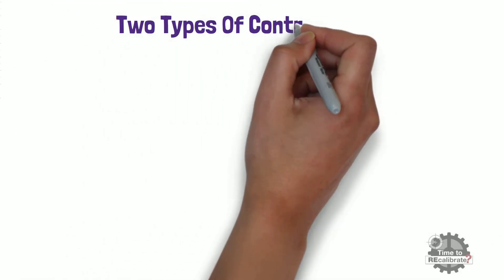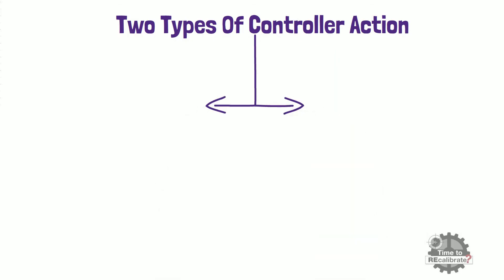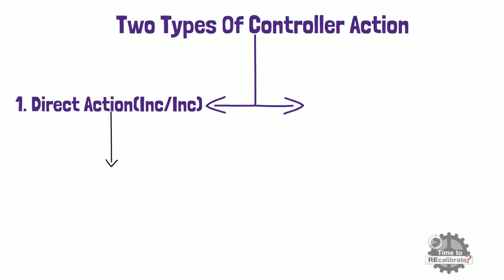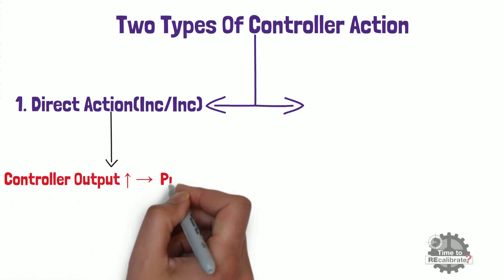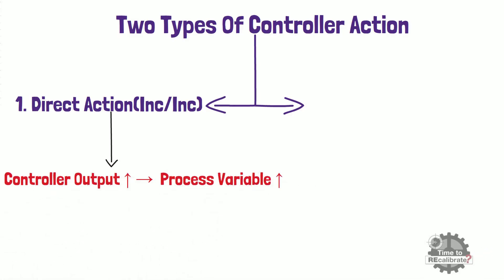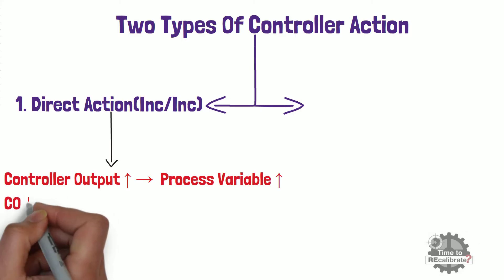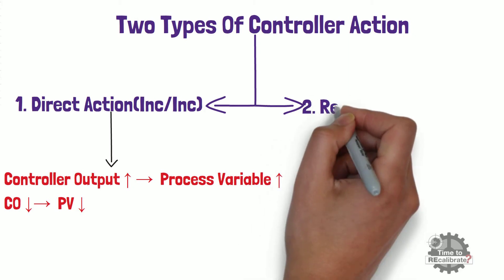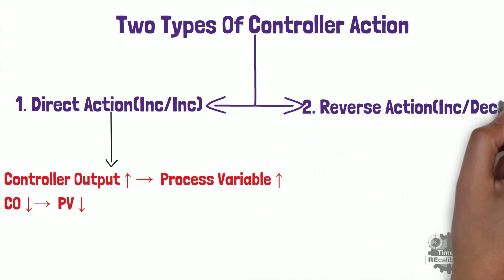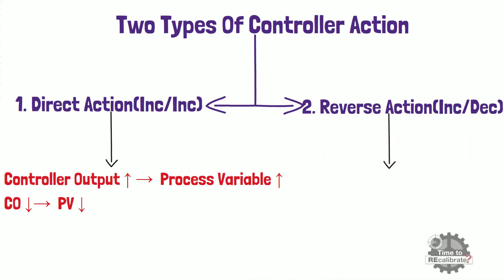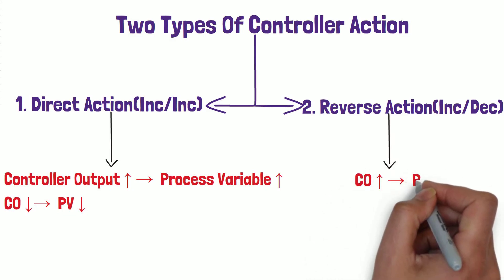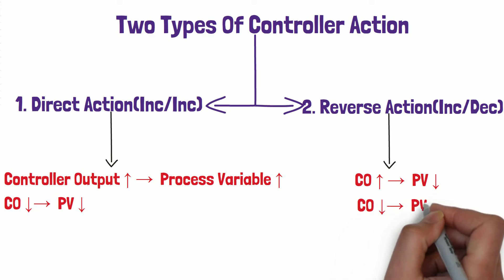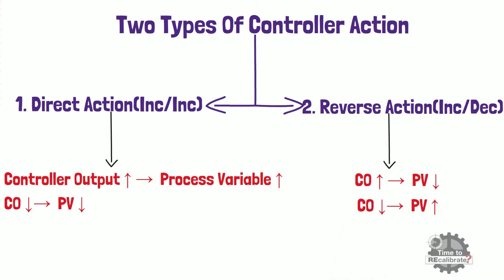There are mainly two types of controller action. The first type is direct action. In direct action, either the controller output increases when the process variable increases above set point, or the controller output decreases when the process variable decreases below set point. The second type is reverse action. In reverse action, either the controller output increases when the process variable decreases below set point, or the controller output decreases when the process variable increases above set point.